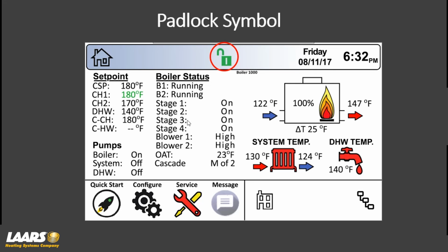We're showing 4 stages. So that's telling me that this is a 1250 or greater, showing 2 blowers. In this example, all 4 stages are on. Both blowers are in high fire or high speed. We have a symbol here for the combustion chamber. We're showing 100% flame pattern. We have an inlet sensor, outlet sensor, and we'll even give you the delta T. We'll show that the pumps are on, or the boiler pump in this case is on, system pump off, DHW pump is off.